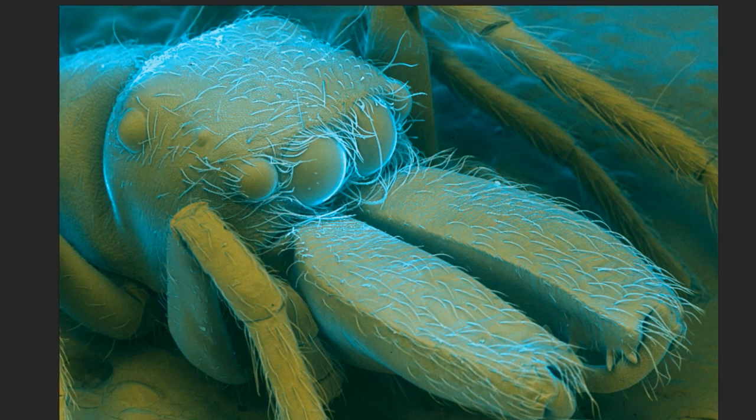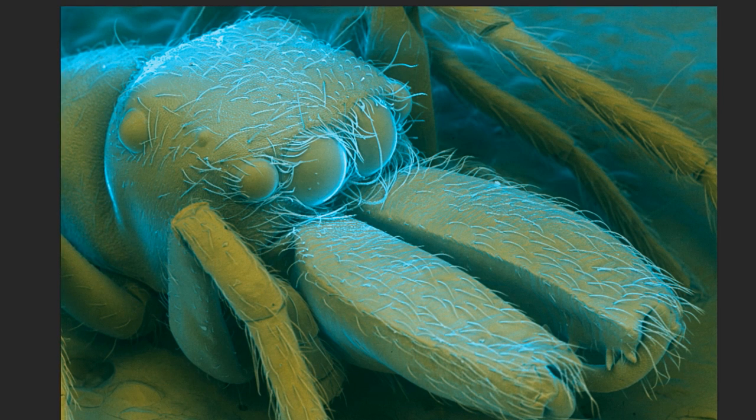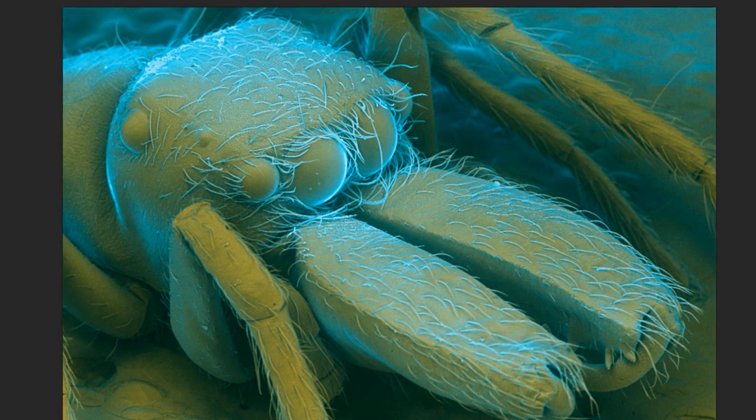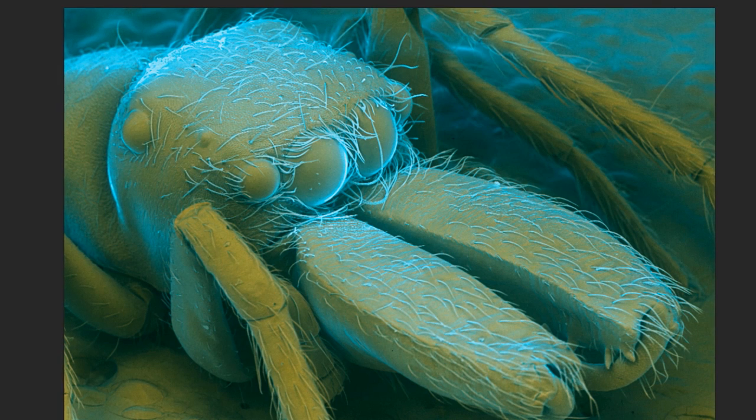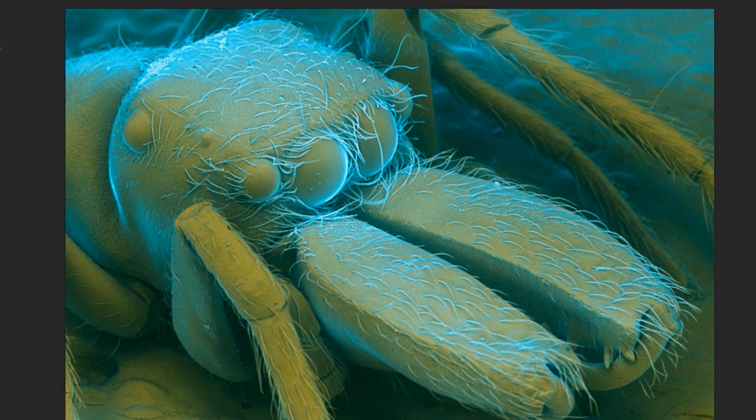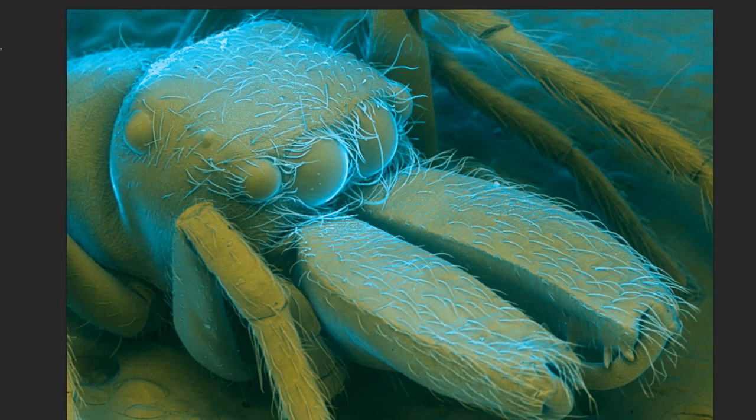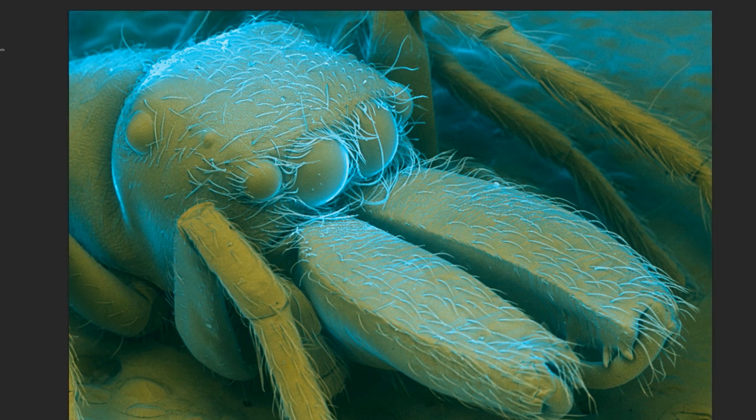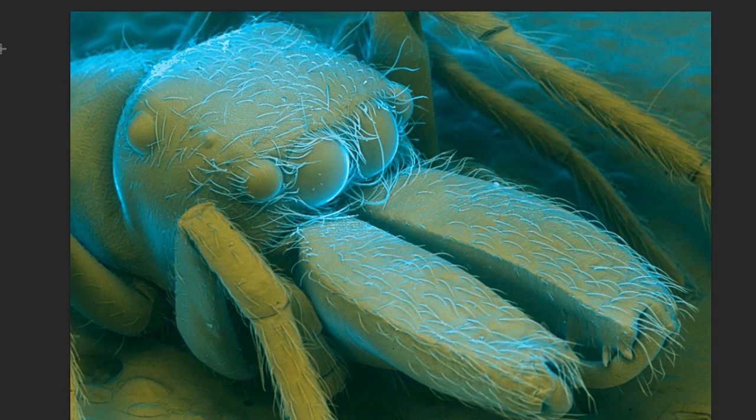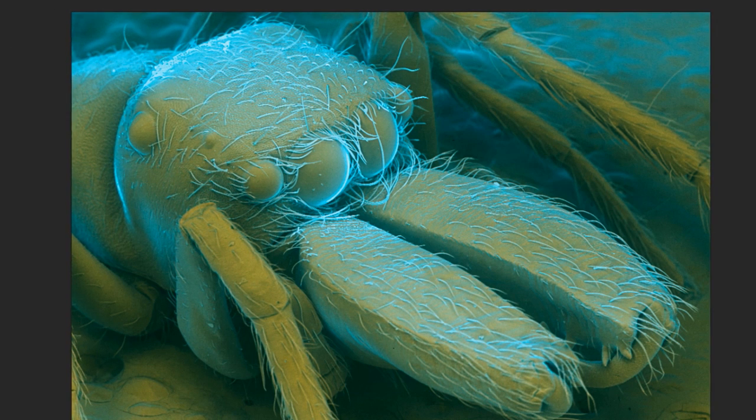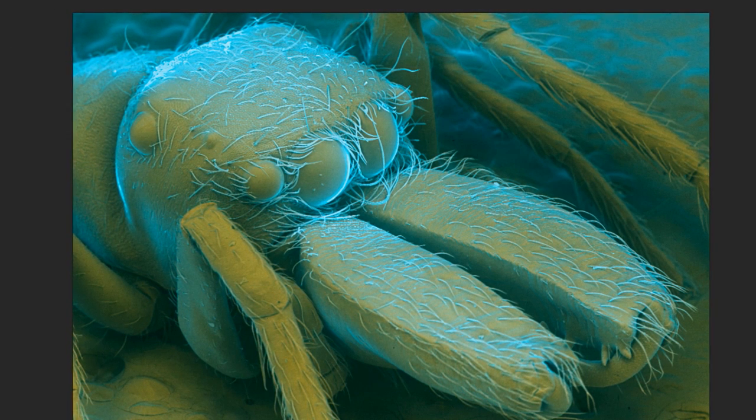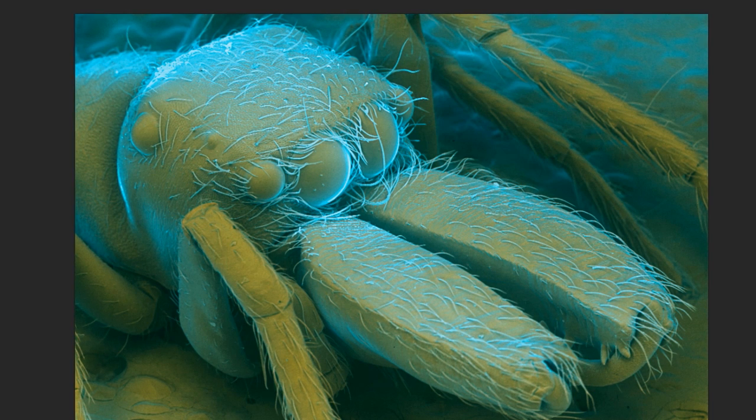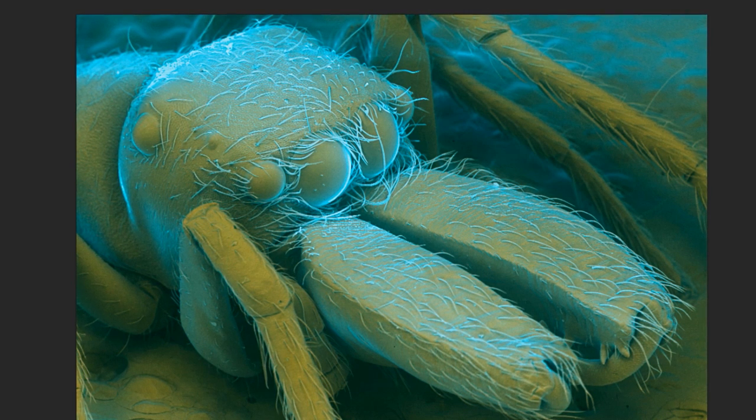This is a full-color spider here. This is a house spider, and it's at about 25x. I should say that this technique works really the best from maybe 20 to about 500x. Above that, it's really tough to get the two images to align correctly, but if you have a really conductive sample, you can find that the alignment works much better to even a high magnification.